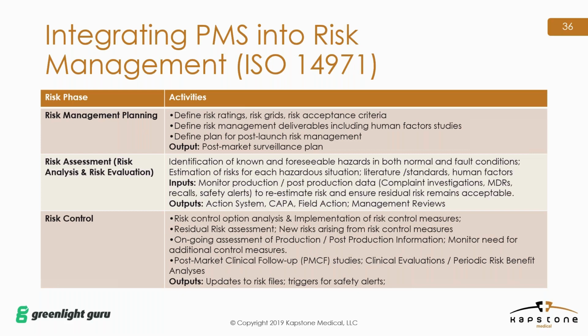And then of course, you have your risk control phase. So you need to take into account any risk control measures that you put into place, and you need to update your risk files and trigger any safety alerts. And also, of course, update your post-market clinical follow-up. Is there something else that you need to be evaluating? Any other type of clinical data that you need, and then doing your periodic risk-benefit analysis based on the data that you've collected.